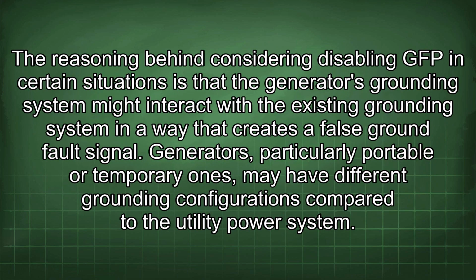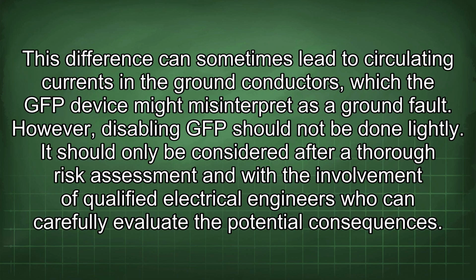The reasoning behind considering disabling GFP in certain situations is that the generator's grounding system might interact with the existing grounding system in a way that creates a false ground fault signal. Generators, particularly portable or temporary ones, may have different grounding configurations compared to the utility power system. This difference can sometimes lead to circulating currents in the ground conductors, which the GFP device might misinterpret as a ground fault. However, disabling GFP should not be done lightly.